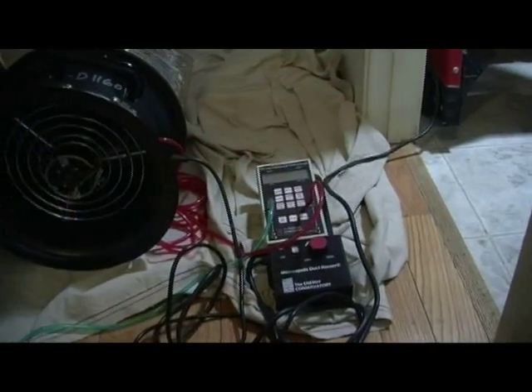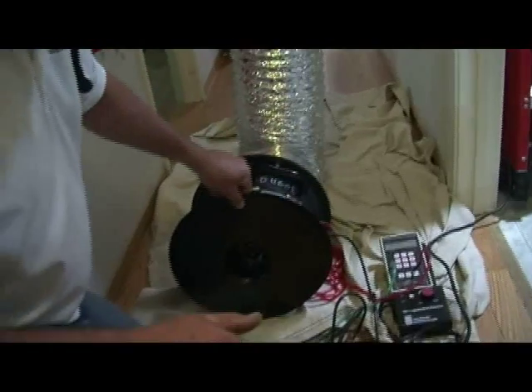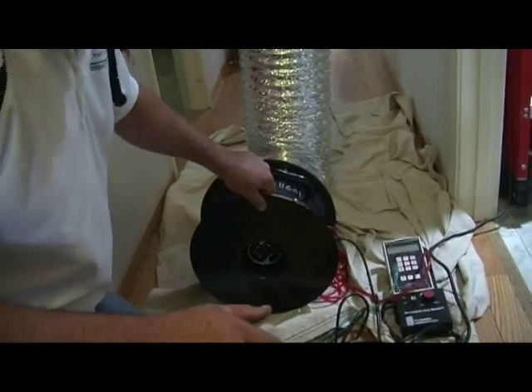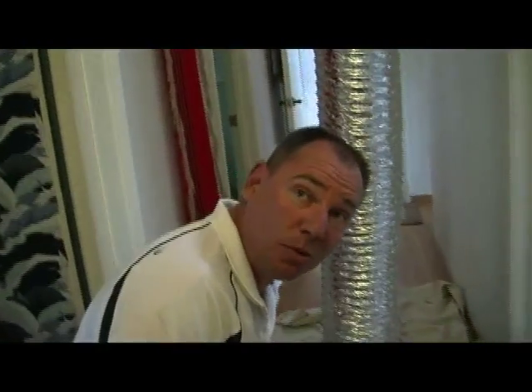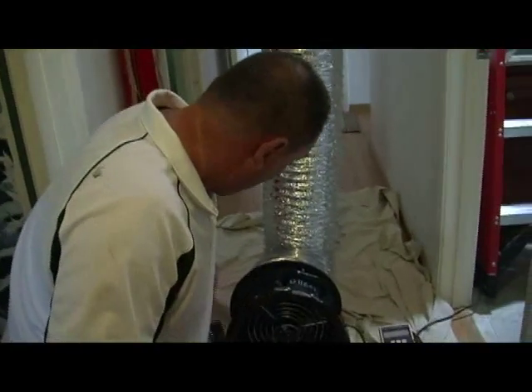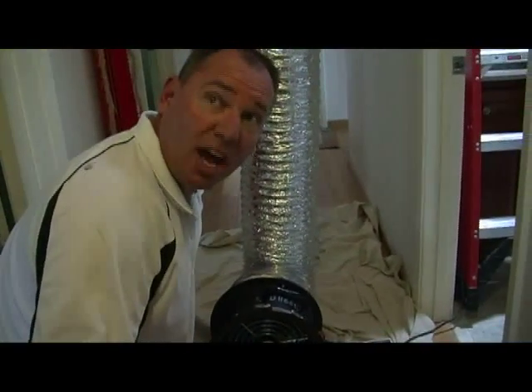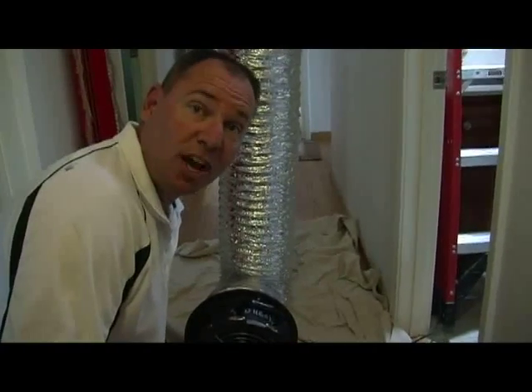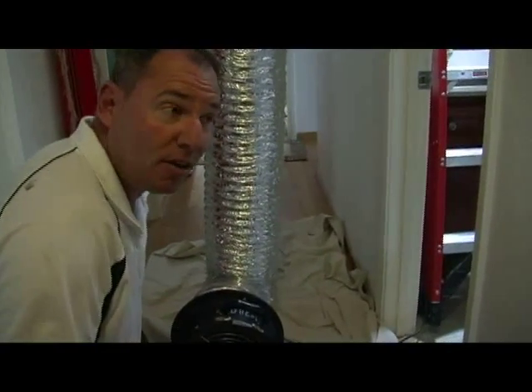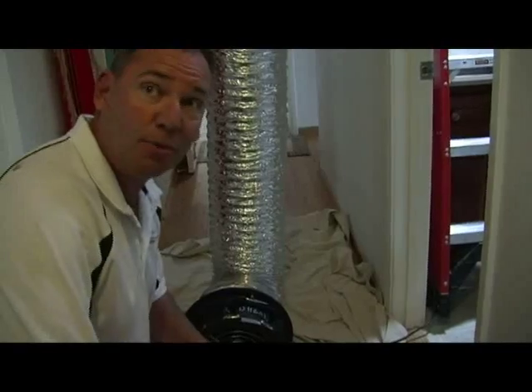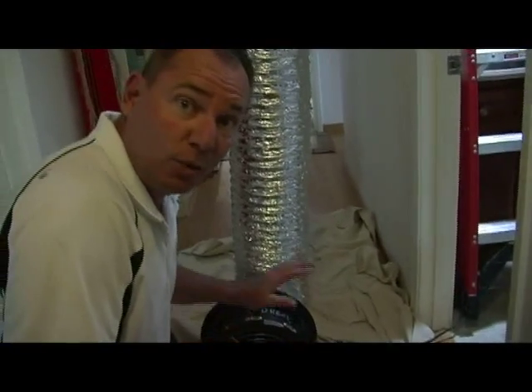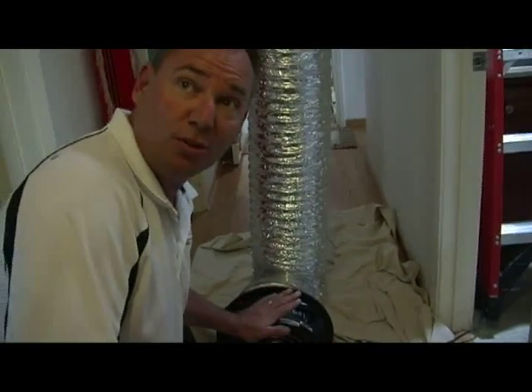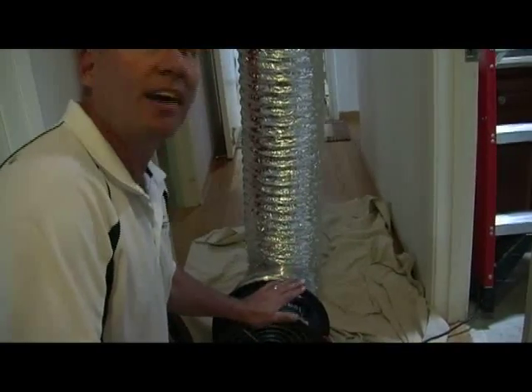And then this is a manometer, and these are the tools that we use to turn the fan on and off, and this is some of the ring gauges that we use, and this is the smallest ring, number 3, that we happen to use with this home. And our measure here was 4%. We were looking for 4%, and I believe that we achieved 4 or less than 5% when we were done. We started with 21, 22, and when we were finished, we got to 4.